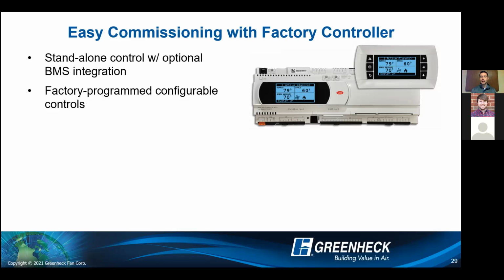And what we do is we utilize a controller from Carel, and all it is a skeleton. And I'm sure some of you are familiar with it, but what we do is we take that skeleton from Carel and we download all of our proprietary knowledge, the logic and the sequencing that we've built over the last 20 to 25 years of doing this type of equipment. And then it's factory programmed exactly how it was ordered. So for example, if it was ordered with duct pressure supply fan control for a multi-zone VAV type application, it will come programmed with duct pressure supply fan control. So all you have to do is tie in that duct pressure sensor in the field and then set that appropriate pressure you want to maintain.